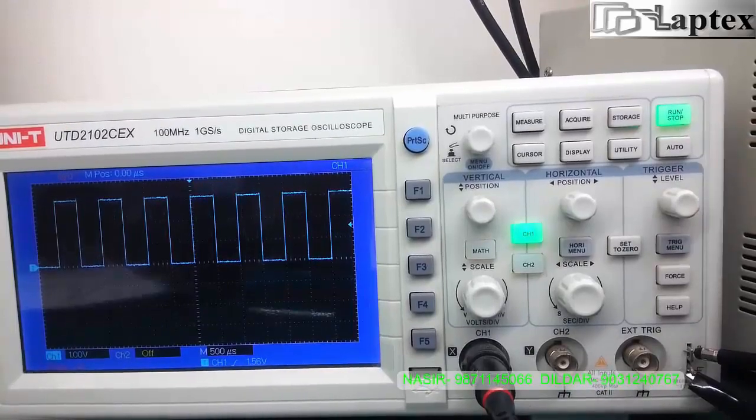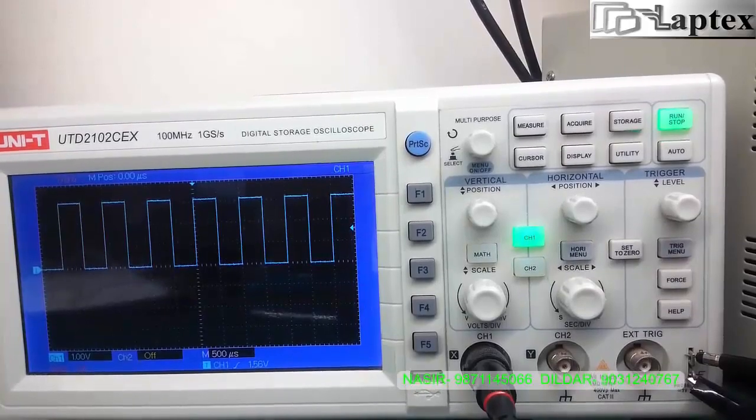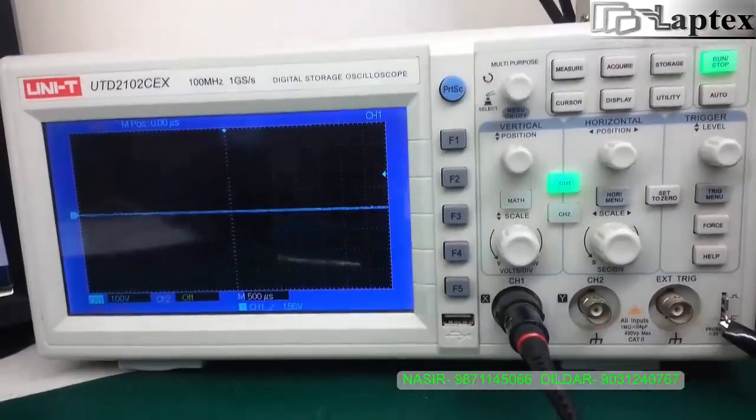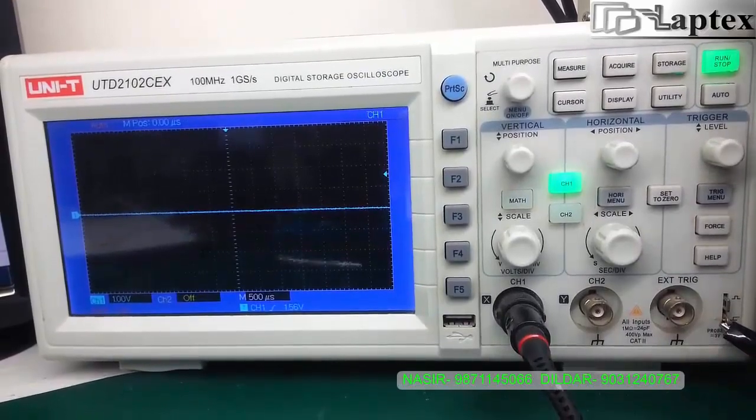Put the probe in the square wave position that you can see here, and then just press auto. You will get your channel calibrated that is ready to use for measuring any signals. Now let's see another point.